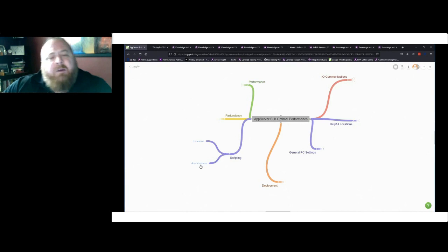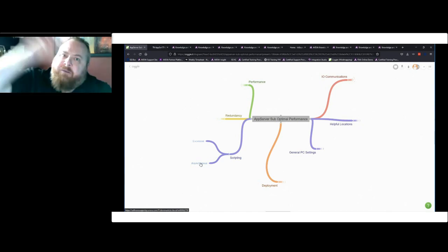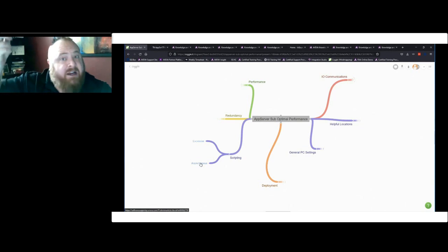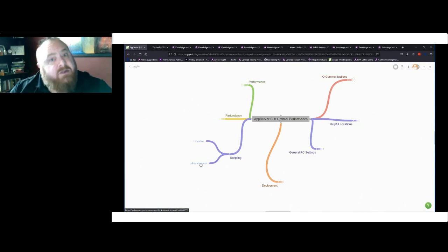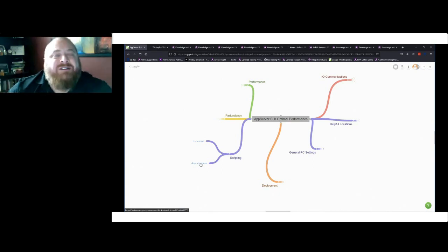And another big one I see is, if we understand how the execution of objects works in AppServer, it's helpful to think of a clock hanging on the wall that has a second hand, completing a revolution around the clock in 60 seconds. The engine scan is doing that too. It's not taking 60 seconds, but depending on the version, it's taking either one second or half a second. In that amount of time, it's doing a whole bunch of stuff, right?